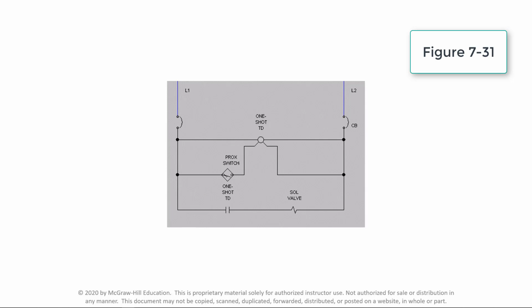The proximity sensor is positioned to detect the passing of a product. When the product passes the proximity sensor, the sensor's contact provides a trigger signal that changes from open to closed and back to open. The timer's output contact closes, causing the solenoid valve to be activated and the one-shot time delay relay to begin its timing cycle.